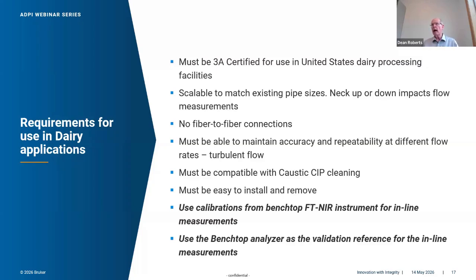And because of the high optical density of a milk sample in the probe, those interference fringes constitute a fairly large portion of the signal. And if you take the fibers off and put them on, it changes the period. And that makes it nearly impossible to transfer a calibration, not only from instrument to instrument, but from probe to probe. And the amount of money that goes into putting together an inline calibration is significant, to say the least, because you have all the reference chemistry that you've got to do, and you just have to collect so many samples to be able to get the range of values necessary to have a calibration that it becomes cost prohibitive to do so.